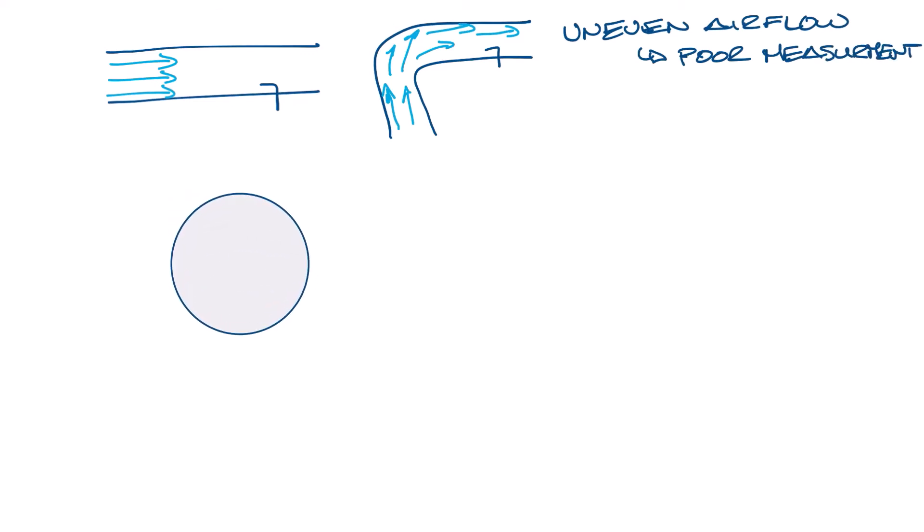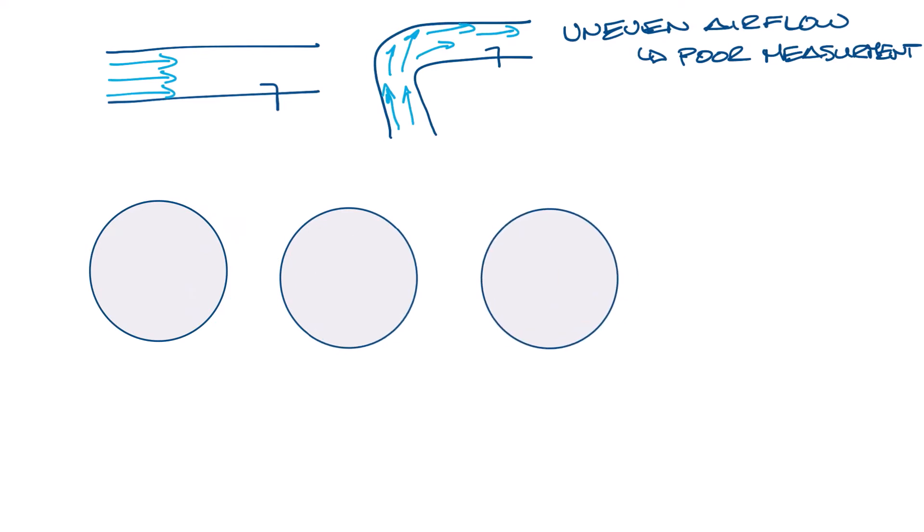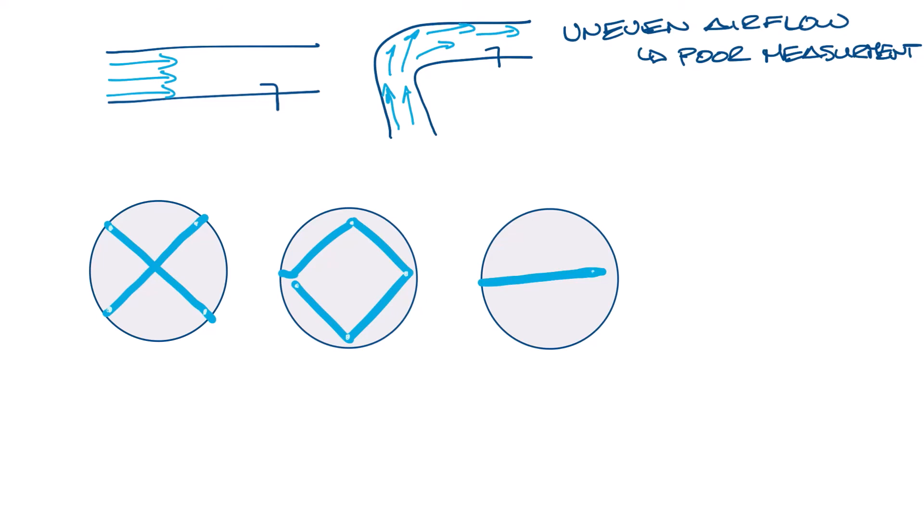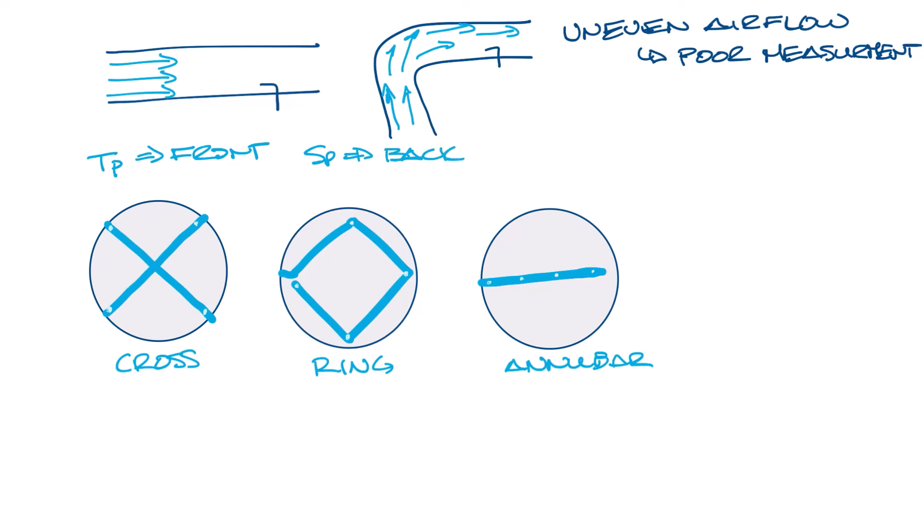So let me put a couple inlets here and let's look at different flow sensor types. So you'll frequently see a flow cross sensor and it looks like it sounds it's an x shape and then there'll be four or more openings on the front side to take your total pressure readings. Next you'll see a flow ring or maybe it's a diamond shape but it kind of looks like this and then again you'll have at least four points on the front to take total pressure readings. Least common but you'll still see it occasionally is an anubar sensor which is just a straight line in the ductwork with points on the front to take total pressure readings. So let's label these flow cross, flow ring, and anubar. And so all the total pressure readings are taken on the front side and the static pressure is taken on the back side. And the way we're looking at this is if we are looking into the inlet with the air hitting us in the back of the head.